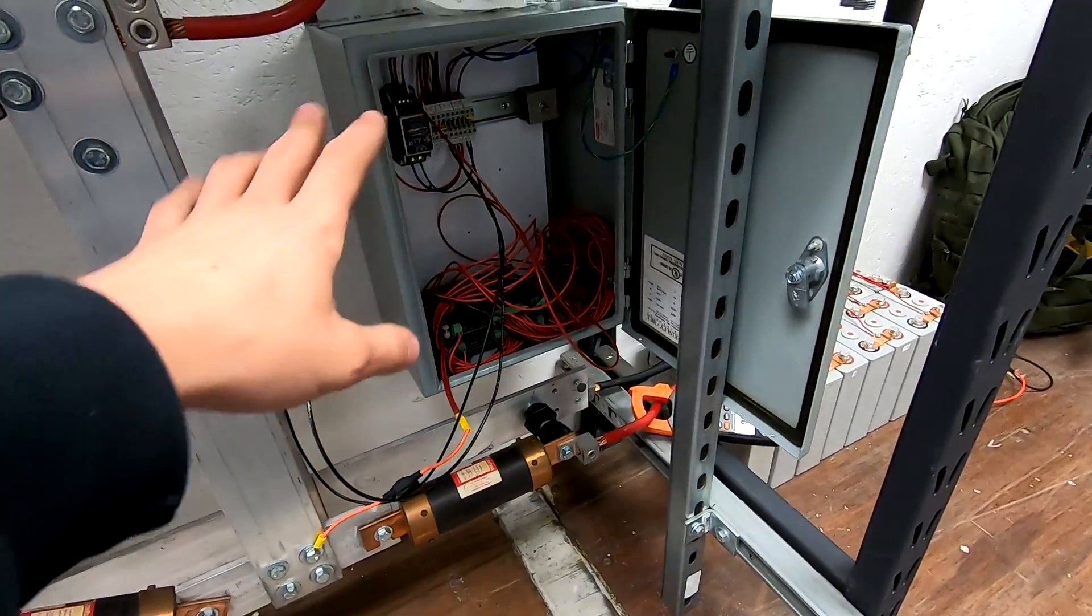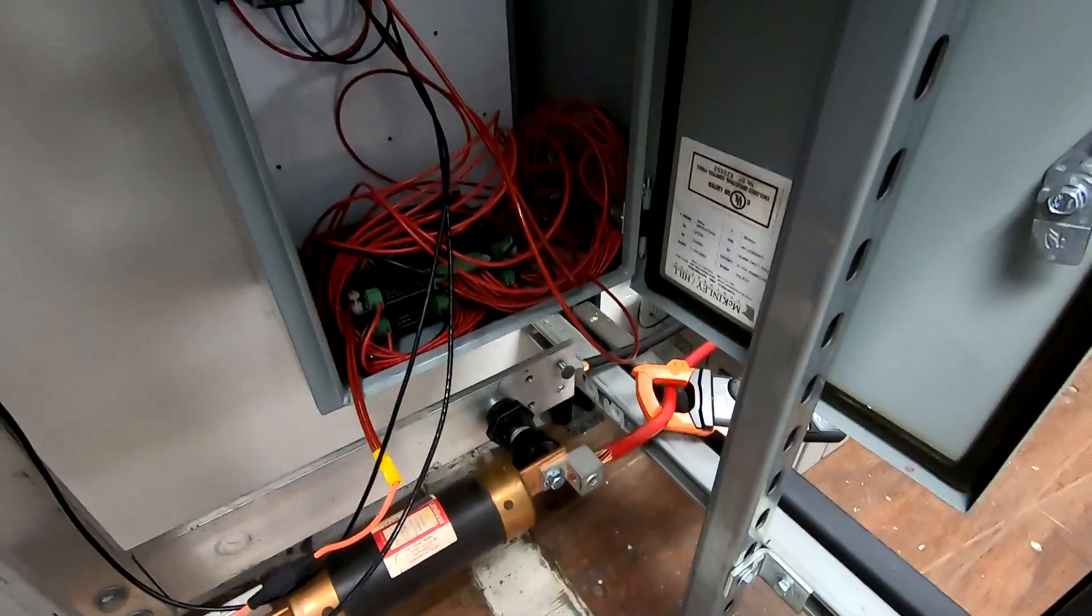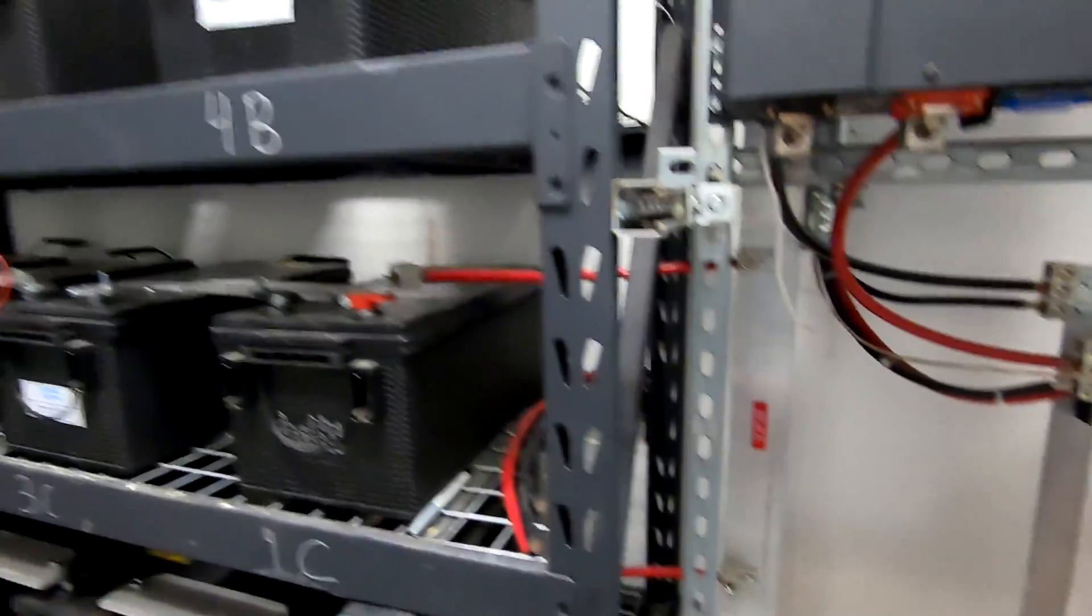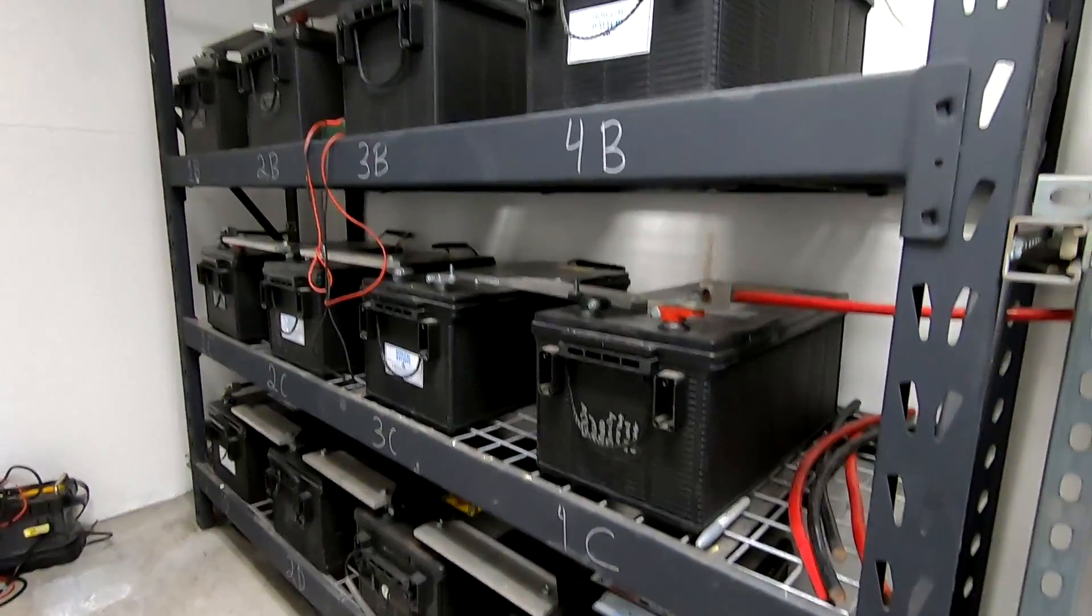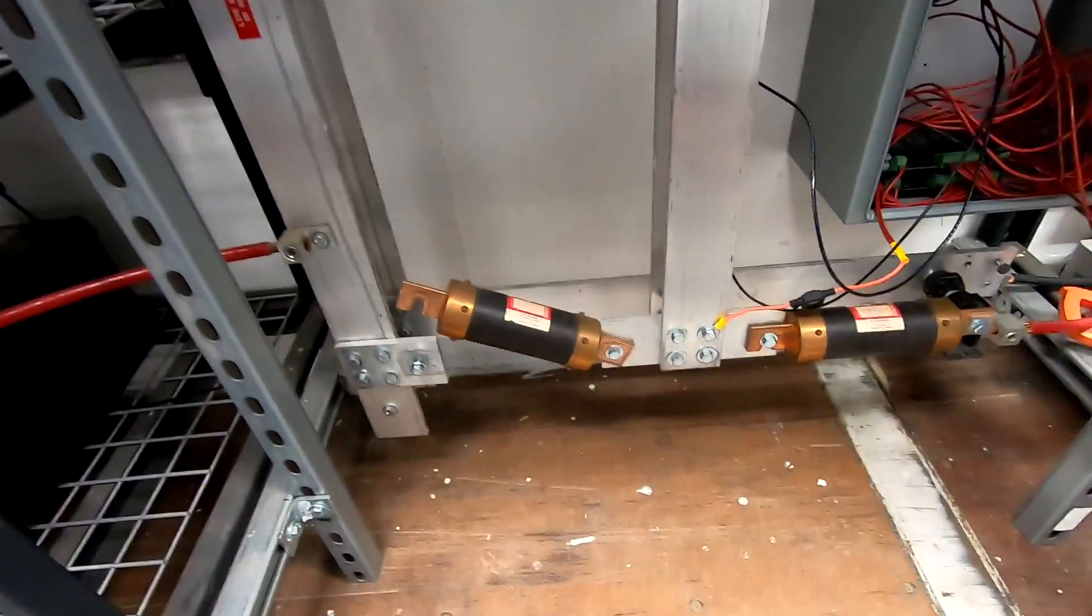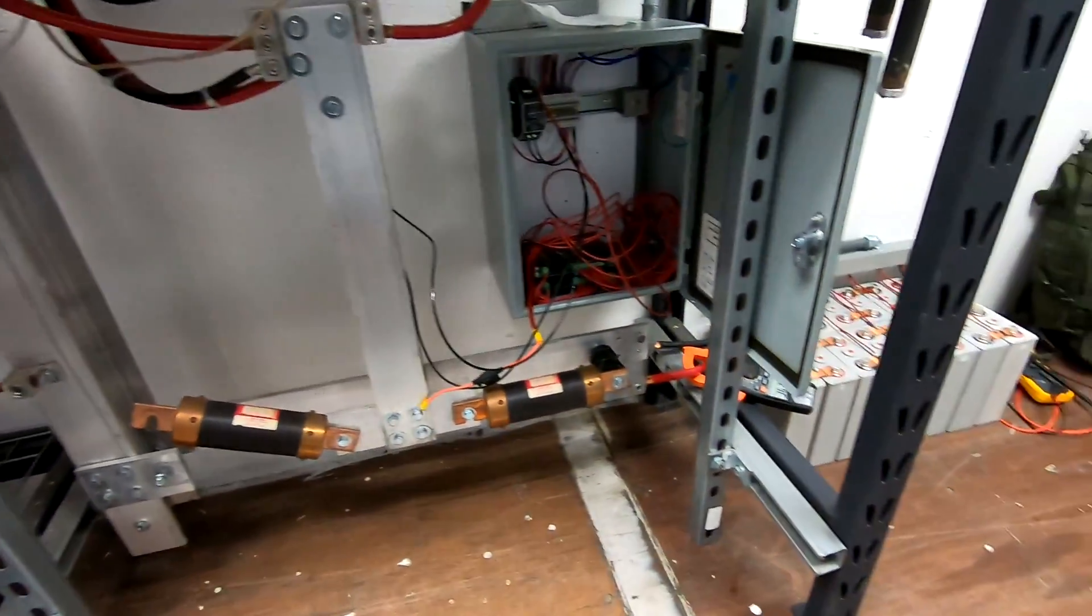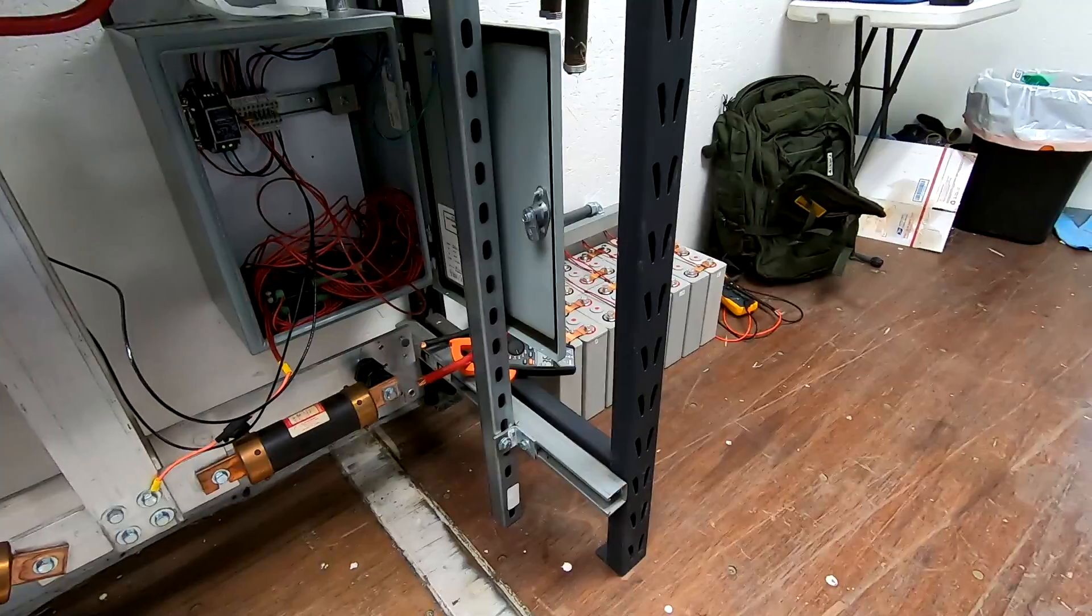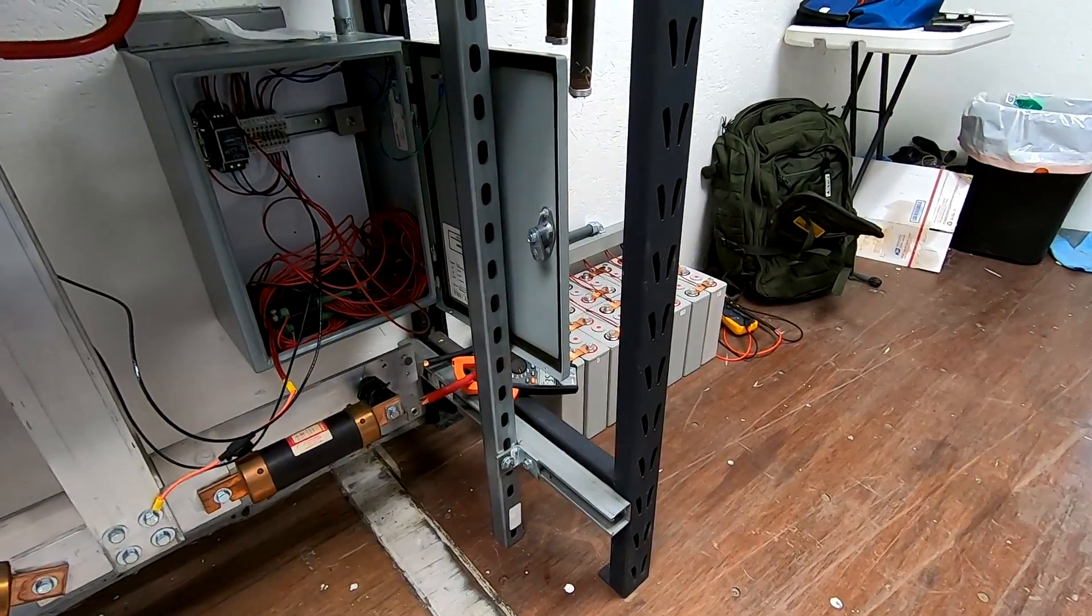Jumping over, I still need to clean up this cabinet quite a bit, but I wanted to show you guys how I came onto these bus bars. I have right here, let me back up, I still have 12 lead acid batteries over here, and those are still bussed on. And the reason for that is, A, is backup, and B, one of the concerns, since these lithium iron phosphate batteries have such an extremely low internal resistance, they have zero problem whipping out hundreds and hundreds of amps.